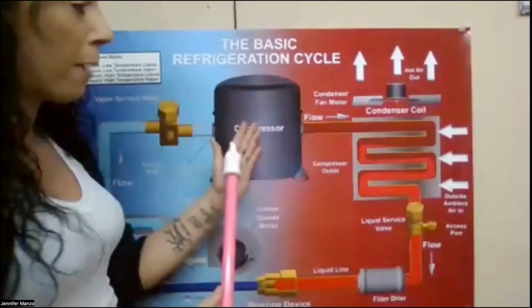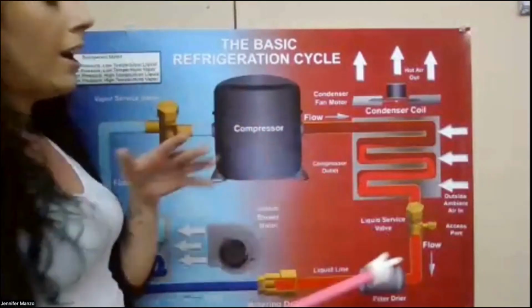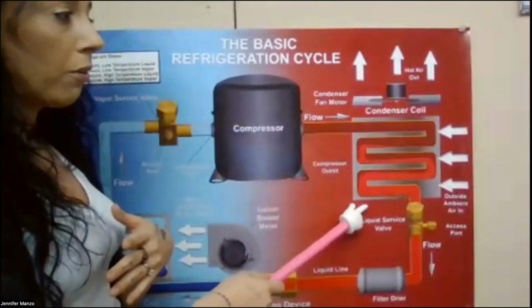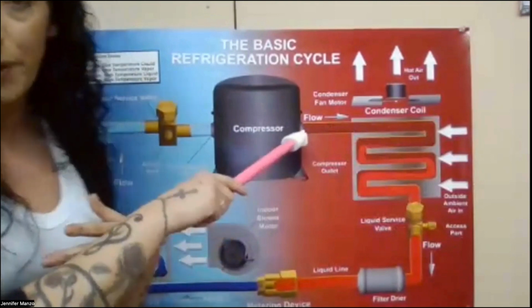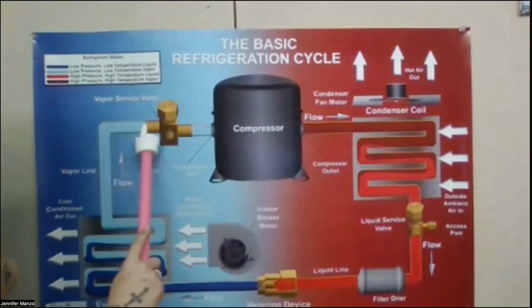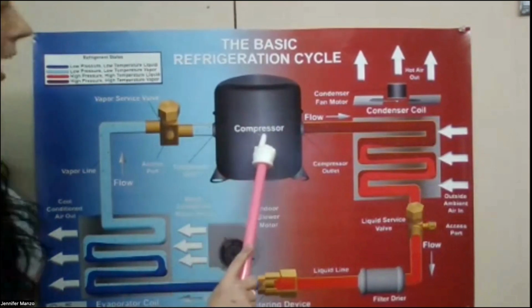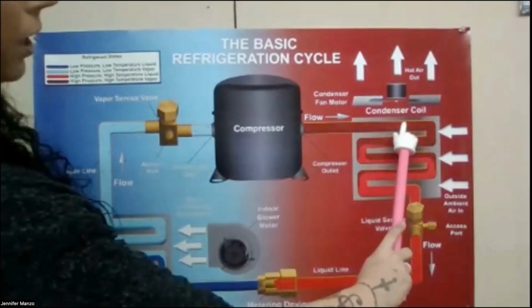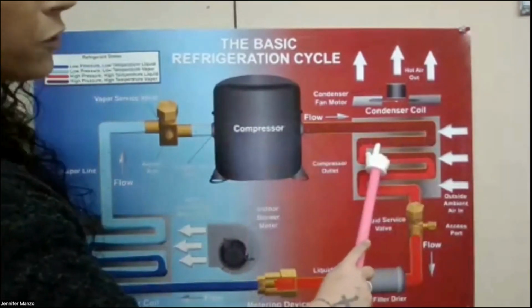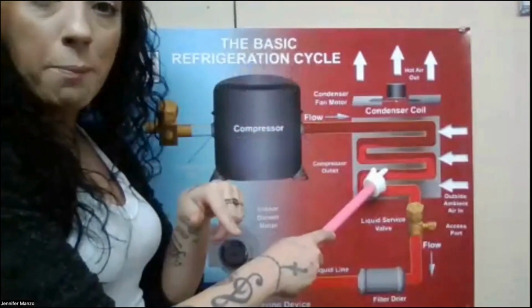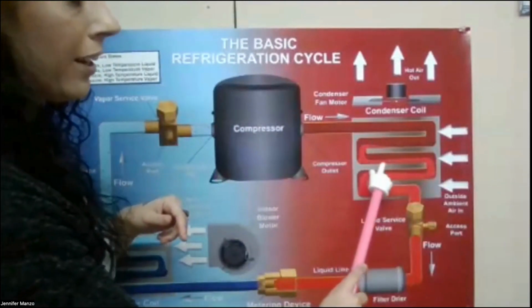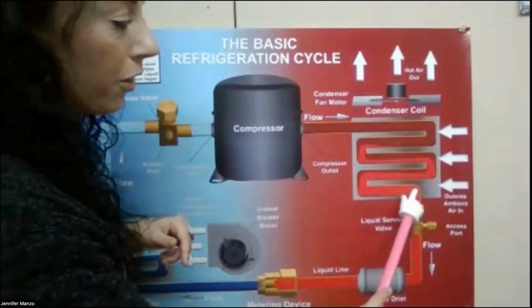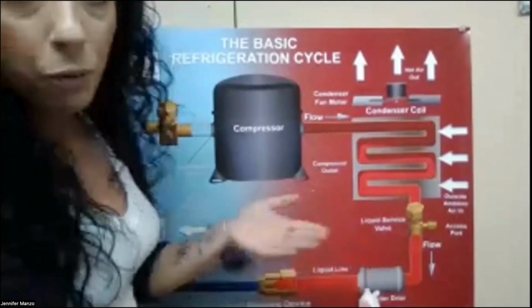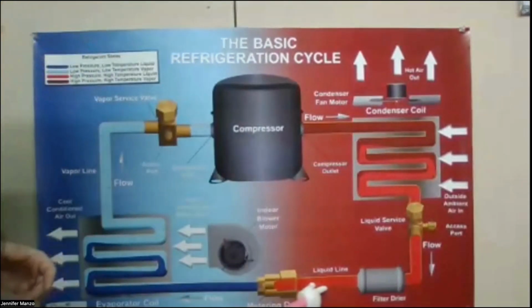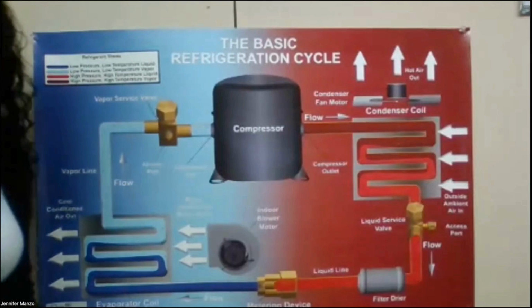If you've got liquid flooding back to your evaporator, you've got a flooded coil, or you've got a restriction. Or you've got an overcharge. If you have too much liquid refrigerant, it will back up into the compressor and break it. That happens a lot. So you have a low temperature, low pressure vapor coming in, and you have a high pressure, high temperature vapor going out. And then once it's halfway about, you can put a thermal imager on the coil as it's working, and you can actually see the phase change. You can see the different colors of the different temperatures. So as it turns into a liquid, you've got it coming through the coil, back through the filter dryer, if you have one. Mini splits, you won't see one of those. There's no need for them on mini splits. And then back to the metering device to, again, drop the pressure.